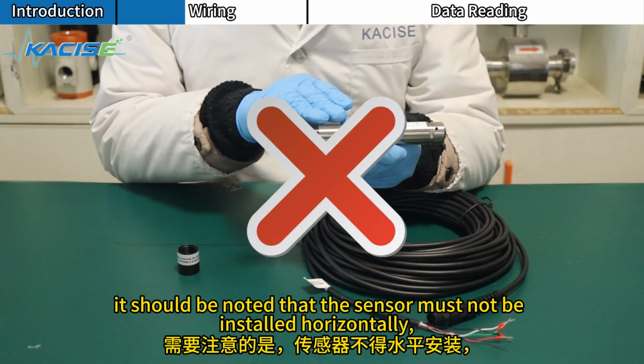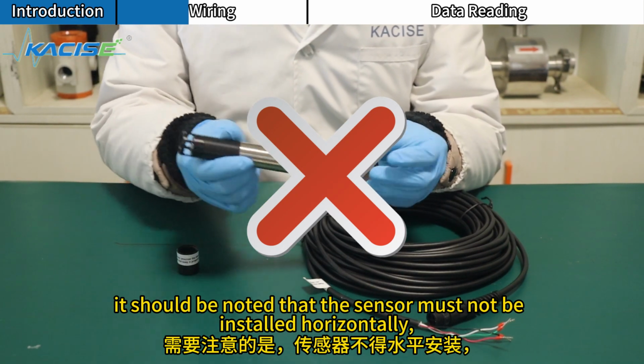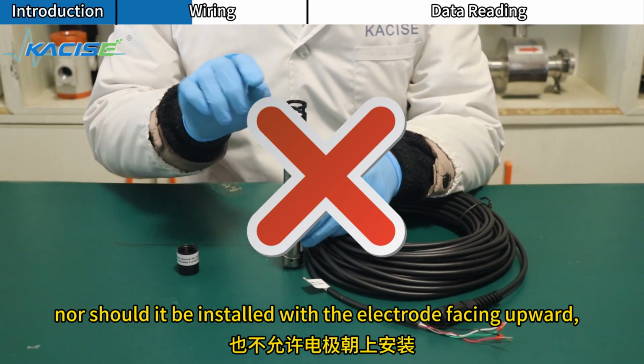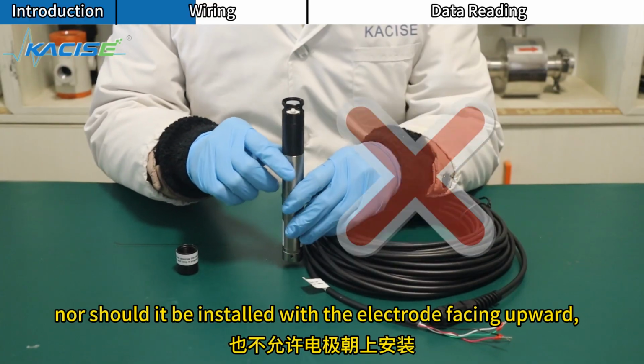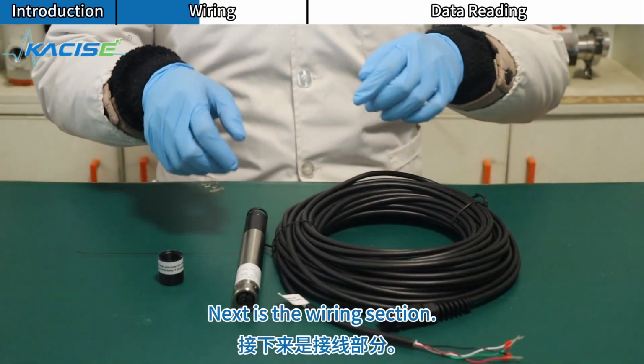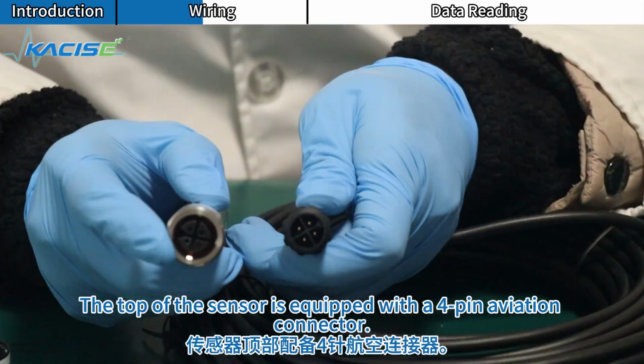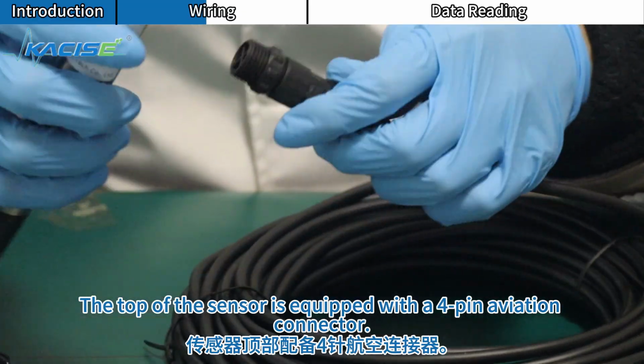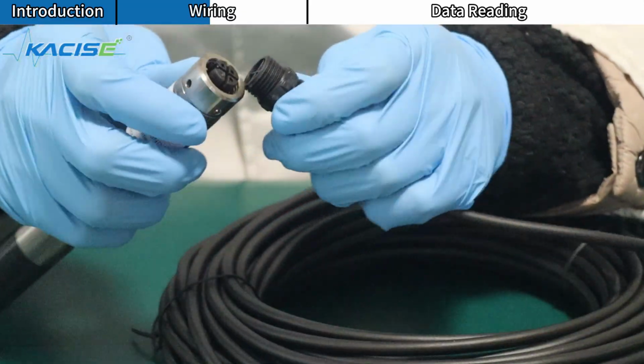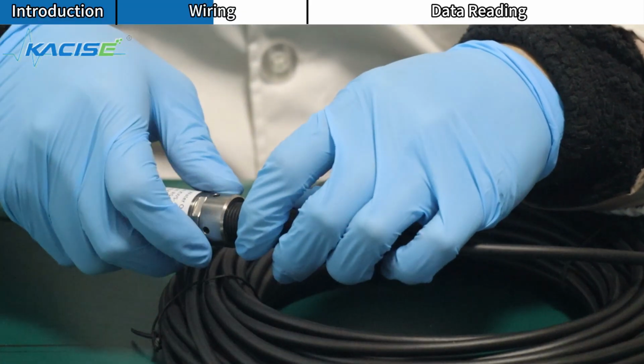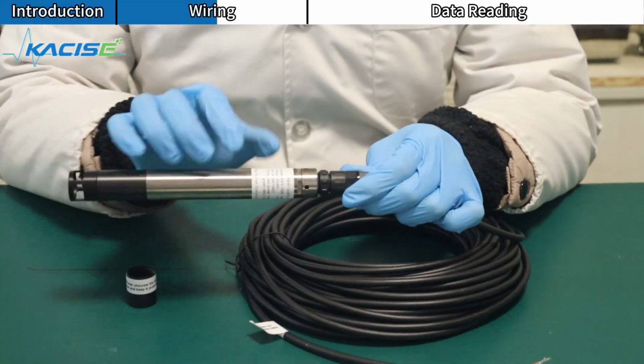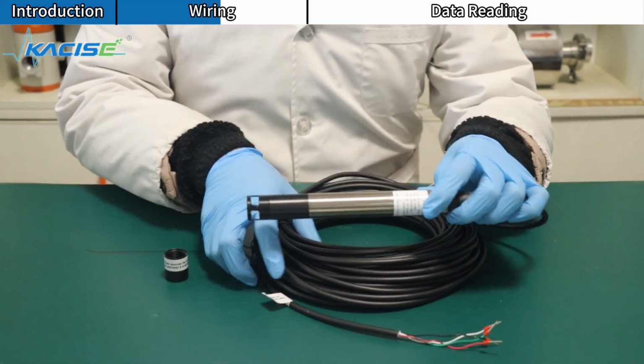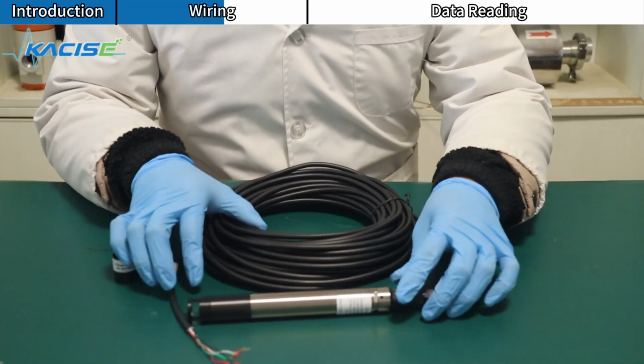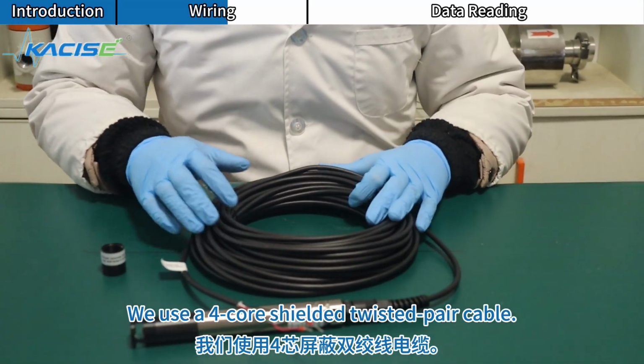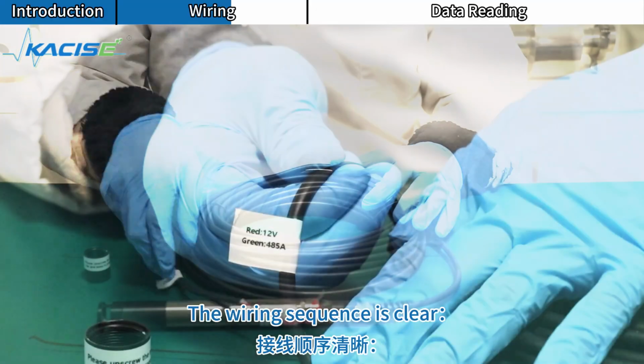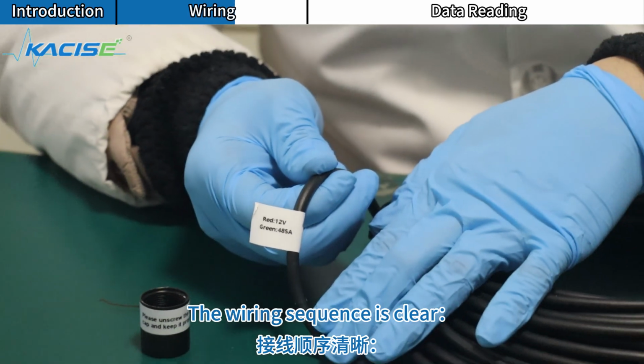It should be noted that the sensor must not be installed horizontally, nor should it be installed with the electrode facing upward. Next is the wiring section. The top of the sensor is equipped with a 4-pin aviation connector. We use a 4-core shielded twisted pair cable. The wiring sequence is clear.